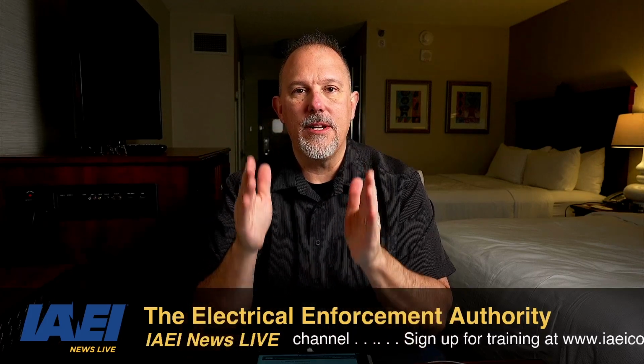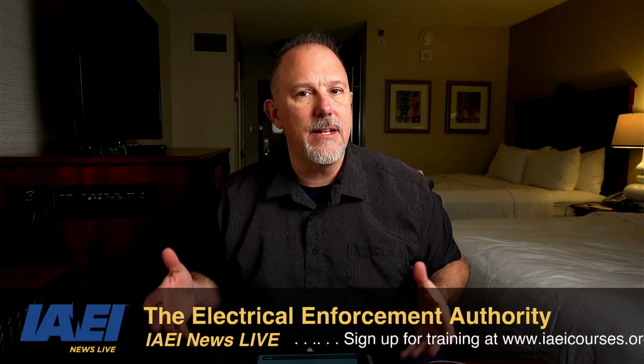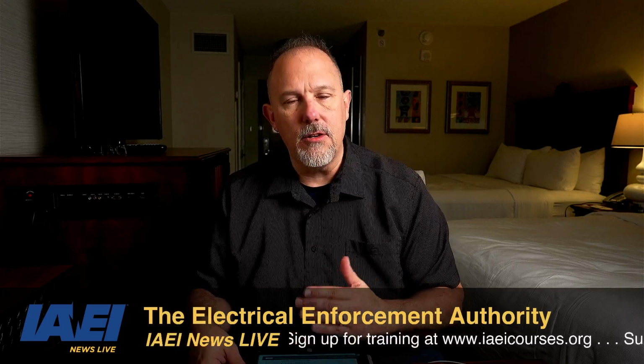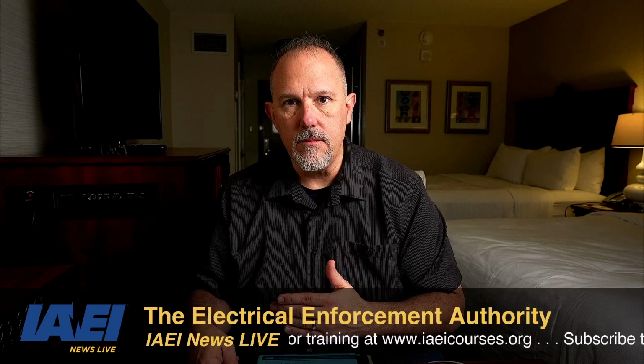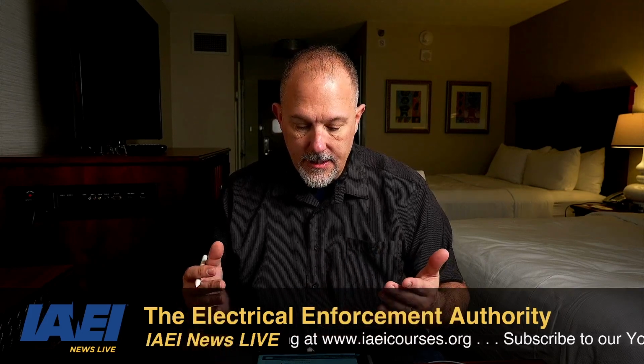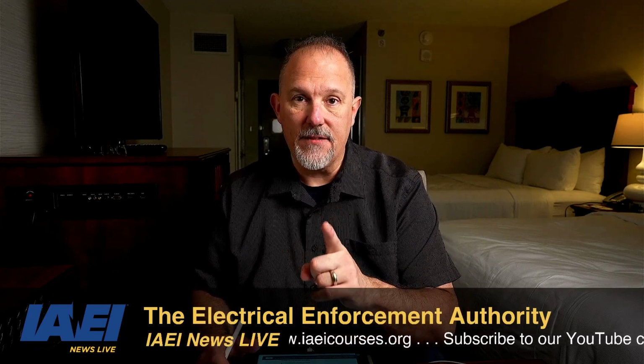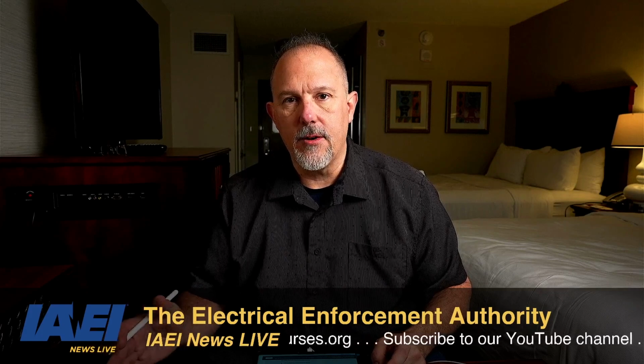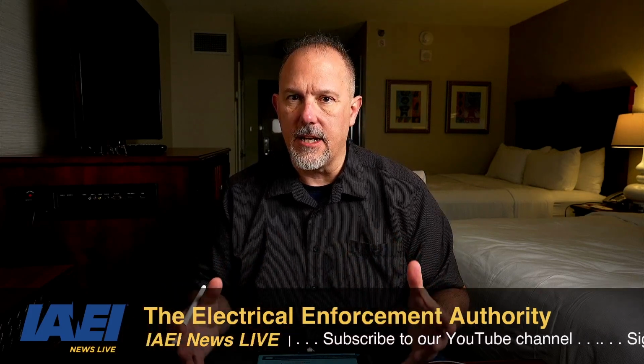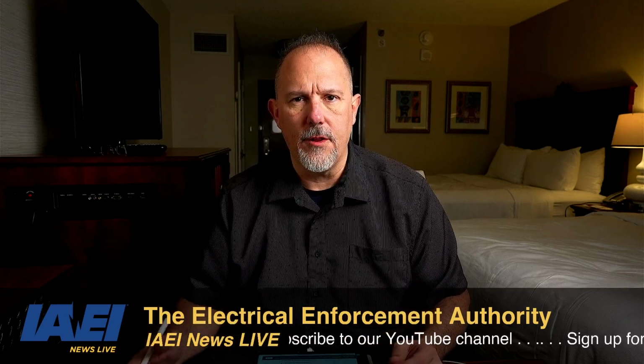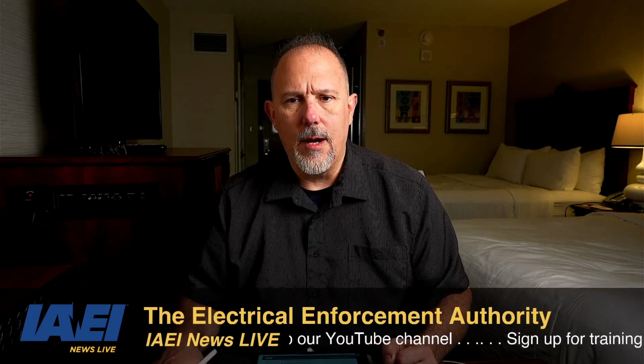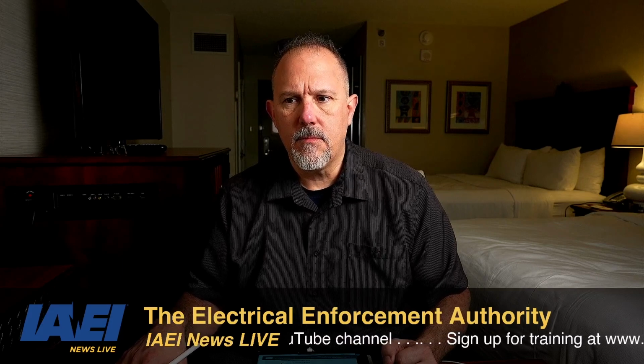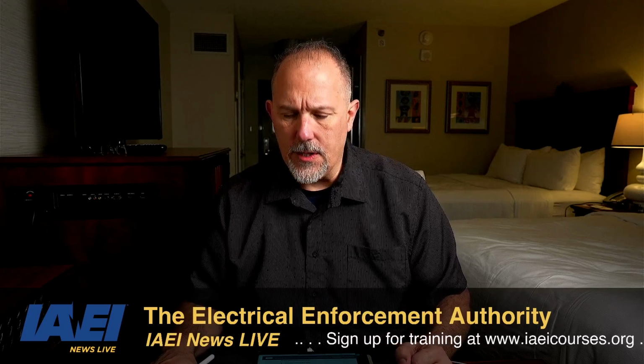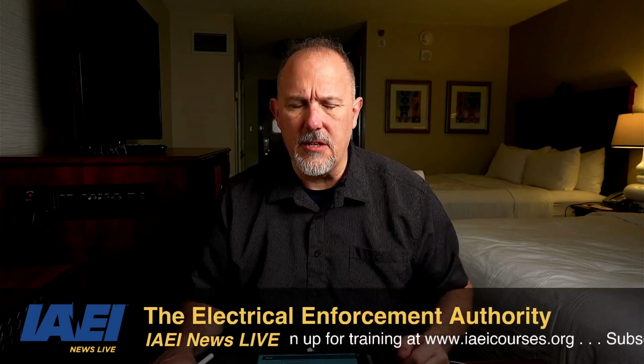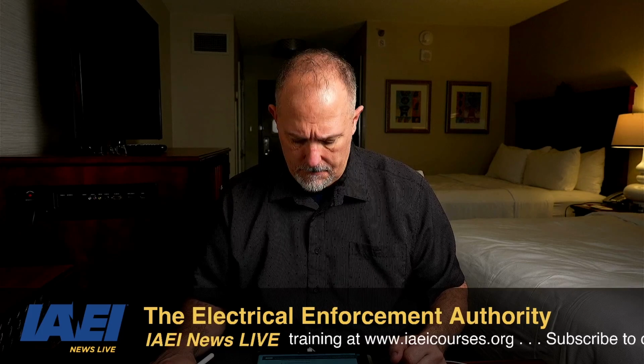So I want to cover generators. This discussion is going to be a look at 445. We'll take a look at what the requirements are in 445. But I also want to take a look at some defined terms, because we have to understand that the output conductors from a generator are a feeder and not a service. So I want to have that discussion. And then I'd like to take a look at the protection and what the requirements in 445 are. What do we have to do to protect generators and their output conductors? And then obviously we're probably going to have a transfer switch. We're going to talk a little bit about separately derived systems versus non-separately derived systems. We'll chat about that a bit as well. All right.